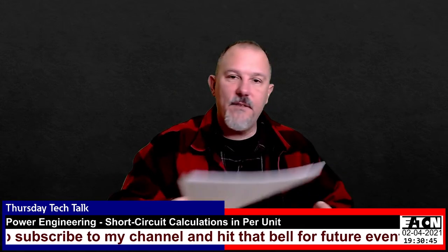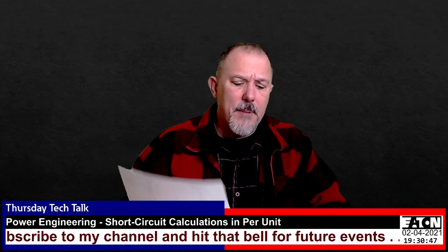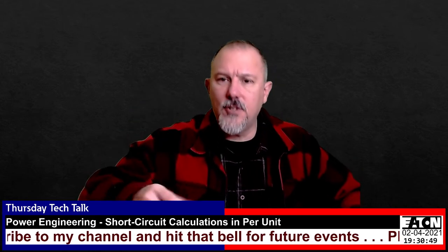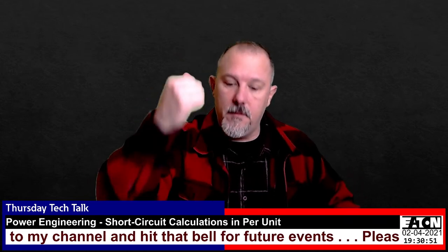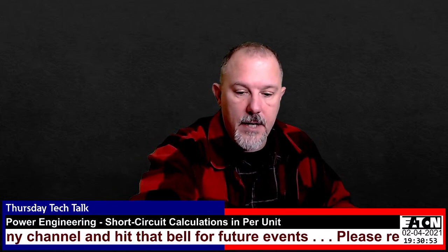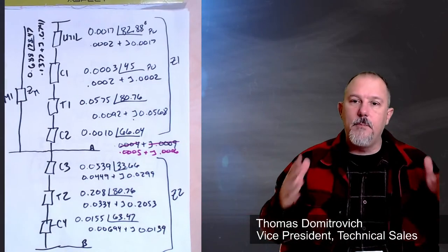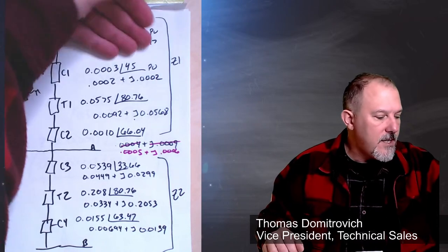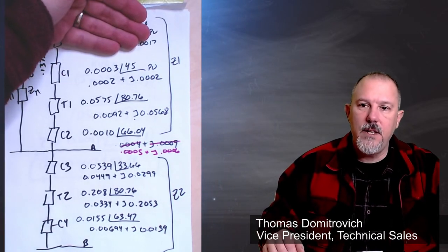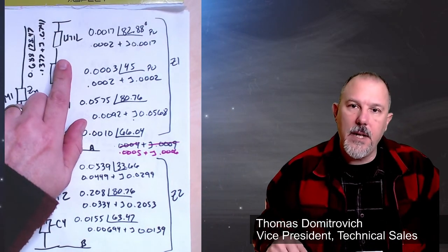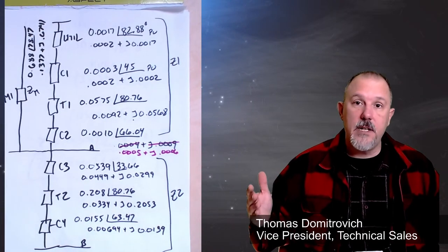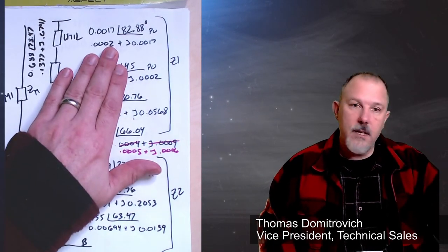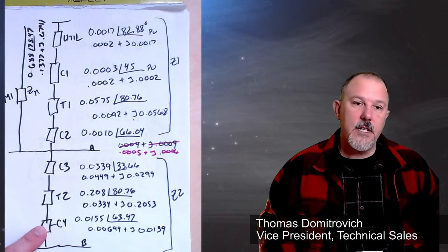We did not do Infinite Bus, but here's what you can do yourself, and maybe send me an email on what you think. To do an Infinite Bus calculation, just ignore the utility impedance. That's all Infinite Bus is. Don't do the utility impedance and do all the calculations.